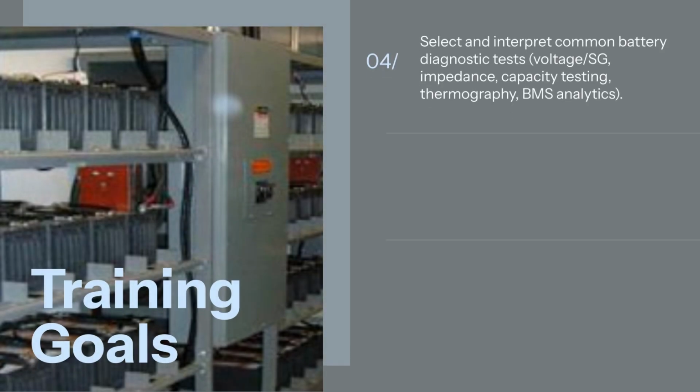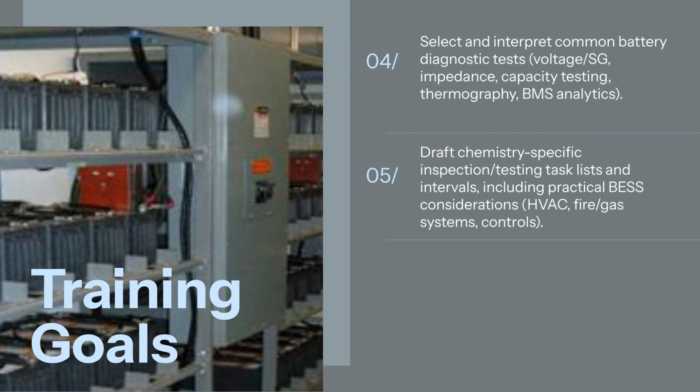Select and interpret common battery diagnostic tests: voltage, specific gravity, impedance, capacity testing, thermography, and battery management system analytics. Draft chemistry-specific inspection and testing task lists and intervals, including practical battery energy storage system considerations, HVAC, fire and gas systems, and controls.